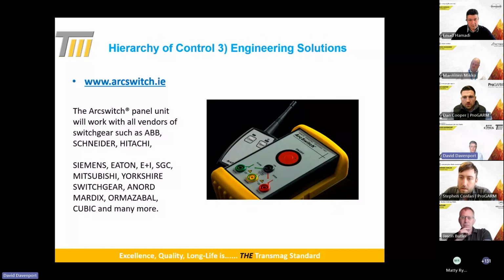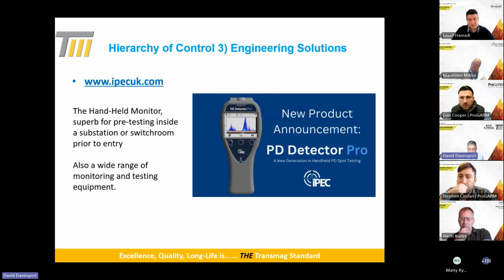So there's always a way around being able to treat those high levels of calorie per centimetre squared. If we go to the Hierarchy of Control 3, Engineering Solutions, I came across this arc switch, which is a genius device for remotely switching breakers. There's also a company in Manchester called PSI Group who manufacture retrofit breakers - 11 kV retrofit breakers - with their own individual remote switching capability. Absolutely excellent, and a good layer to add to the hierarchy of control.